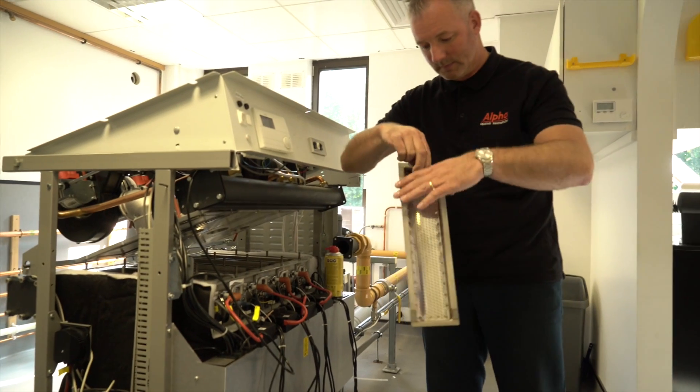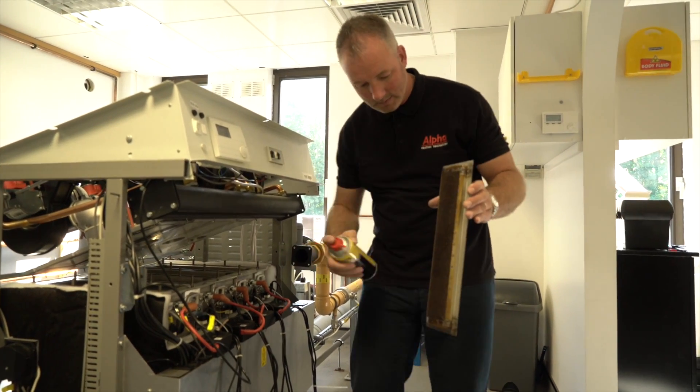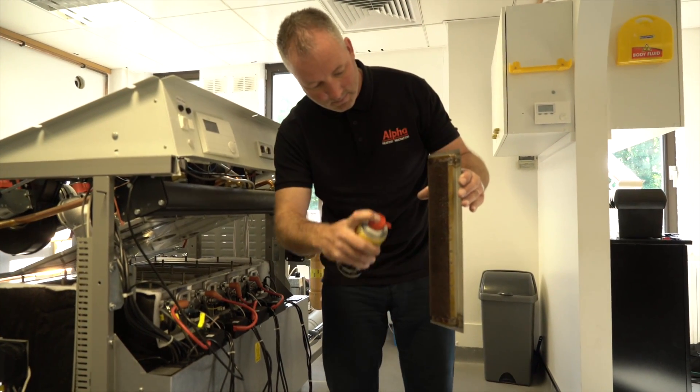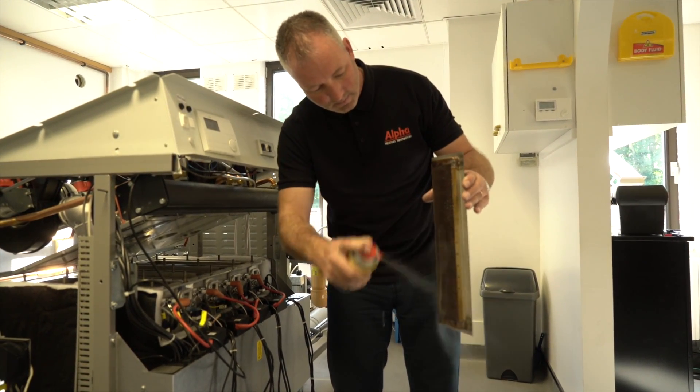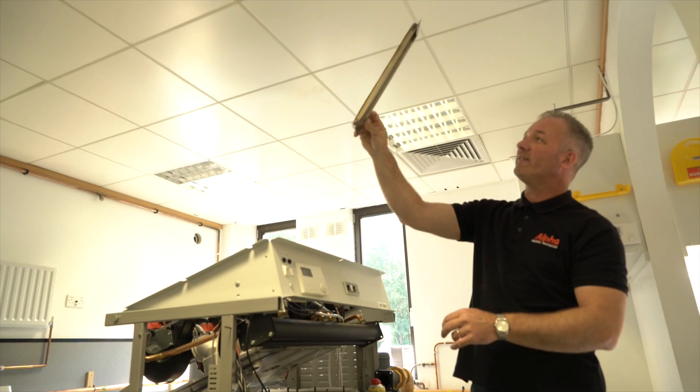Remove each burner. Inspect condition of frame and burner mesh. Dry clean the burner using compressed air working on the flame side.